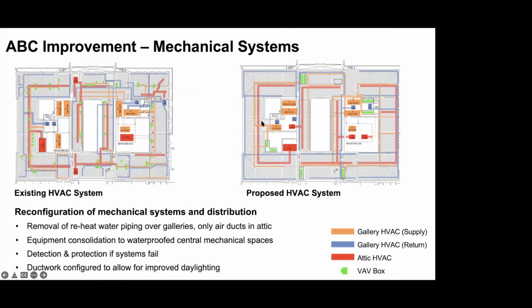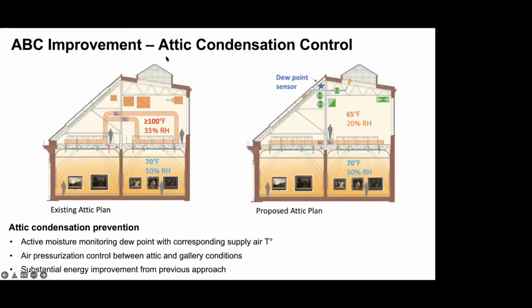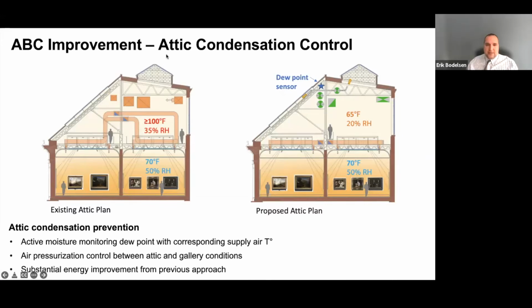As you can see, we significantly consolidated mechanical equipment, with the large colored boxes in the center of the plan being air handling units that were replaced as part of this project. Highlights of the improvement include removal of reheat water piping over the galleries so that only air ducts will be in the attic going forward, equipment consolidation to waterproof central mechanical spaces, and detection and protection if systems fail. For instance, if a leak is detected, a sequence is initiated to shut down the pumps and close off the valves to the water systems that feed all the VAV boxes, and it allows the Met to react in a timely fashion without introducing a flood threat.